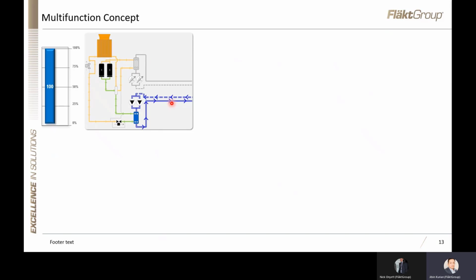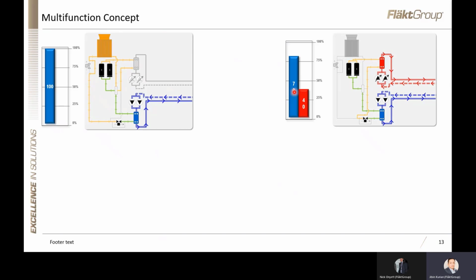So how does this work? Here in the animation, you can see how. In the first animation, there is a demand of 100% cooling. In this mode, the multifunction heat pump works just as an air-cooled chiller. So the heating side is deactivated and only the cooling side is activated. And if the demand is 70% cooling and 40% heating, then you will have partial recovery on the heating side. You will use the heat exchanger for partial recovery, and the remaining heat will be rejected to the external condenser.